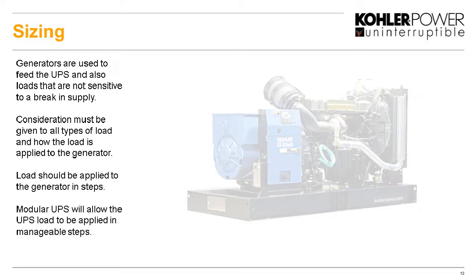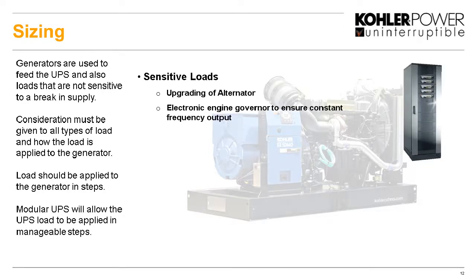So sizing. We have to make sure that we understand what we're going to size. Generators are used to feed the UPS and also for some other non-critical stuff. So when we are actually feeding the UPS, and other sensitive equipment, we have to make sure the alternator is fit for use with the type of load that we're doing. Now, typically with sensitive loads, we may have to upgrade that alternator, but also we have to make sure that the engine runs at a constant frequency, and this is typically controlled by an electronic engine governor as opposed to a mechanical one.